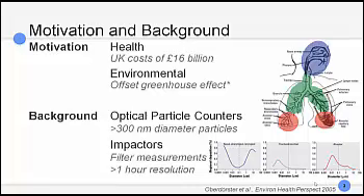And at the moment, there's a lot of use of the optical particle counters because they serve their purpose quite well, because they can count particles individually and size them. But they have this major limitation of not being able to size below 300 nanometers, which is the size that really leads to health effects and also is associated with the short-lived aerosol products in the environment.